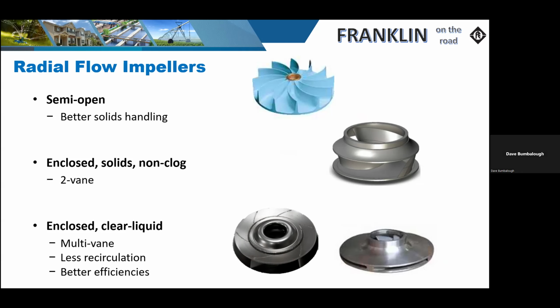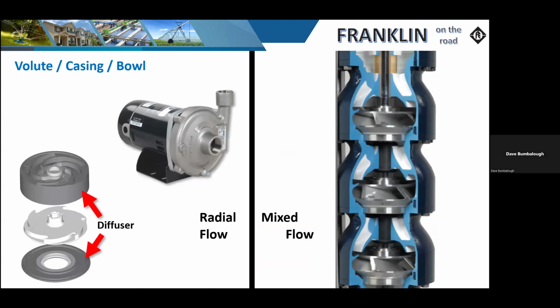And, given its durability and easy manufacturing, that's why it's the most popular in our industry. And it has some other benefits to it. As we go on, I'll explain those. But inside basically a submersible pump, you'll have the impeller with a diffuser surrounding it. That can also be referred to as the volute or the bowl. As the impeller is spinning and moves that water molecule, the diffuser actually guides it to the next stage. And in most cases, you're going to see a multi-stage pump.